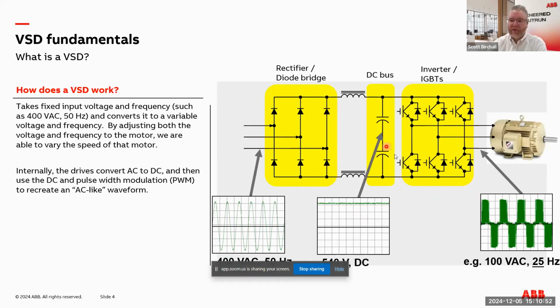One of the reasons I like to show this is for all the people who are involved in installations. Every once in a while, I'll see installations where they've got their 24-volt DC or their 0 to 10-volt analog signal run right next to the motor wires, or they might have safety wires, maybe a vibration switch on a cooling tower, run near the motor wires. In practice, it looks fine, but if you understand what's going on under the hood, you've got 540 volts being turned on and off 4,000 times a second. It's not really good to put that next to your 24-volt wire. That's how you help induce noise and cause problems. So that's why I like to show what's underneath the hood.